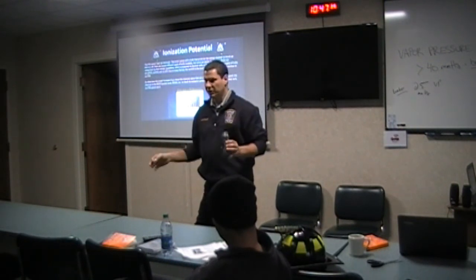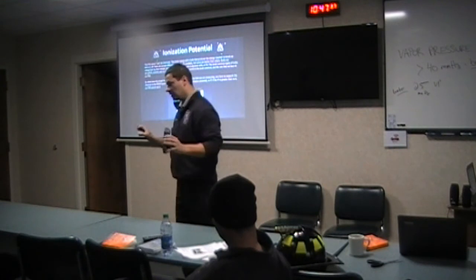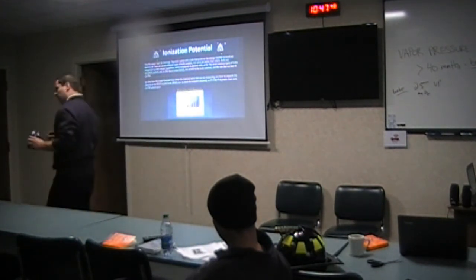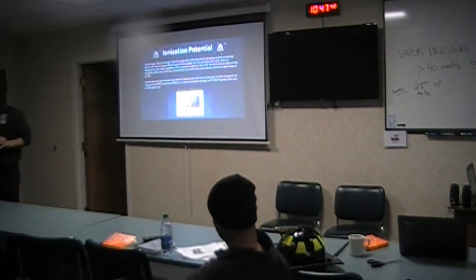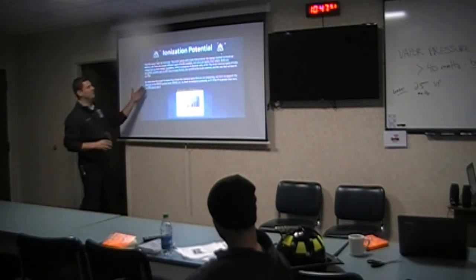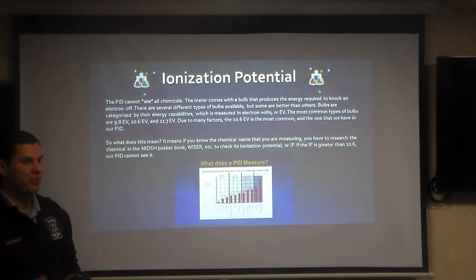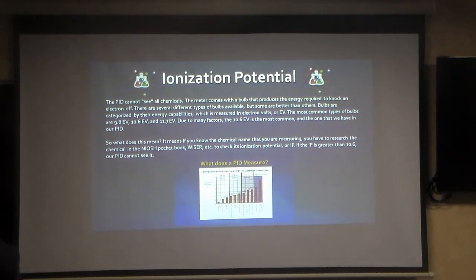The ionization potential, and this is very important, the ionization potential for the gas has to be below 10.6 electron volts for this PID to see that gas, okay? There are different types of bulbs that are available, but the 10.6 bulb is the most common, all right? The 11.7 bulb is out there, but the shelf life of the thing is like 3 or 4 months and you have to replace it. So typically hazmat teams and fire departments use the 10.6 bulb, okay?